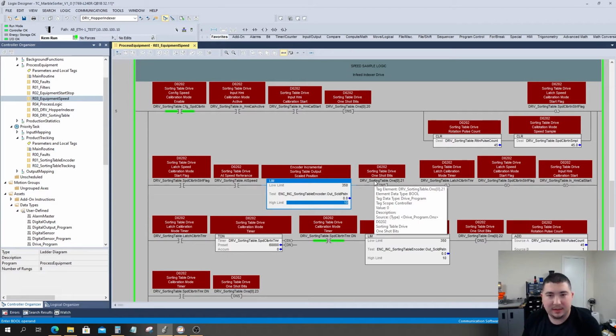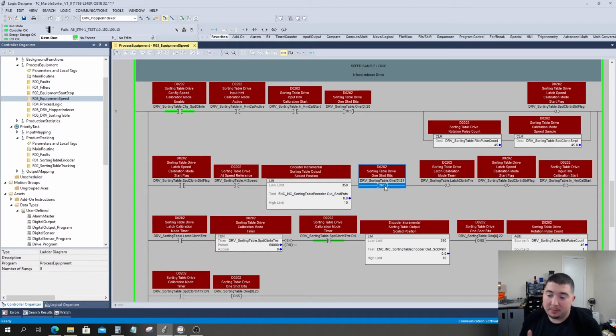We only really need to see it that one instance when it does a one shot, so that's why we have this, but we have a little bit more of a window here so that if there's a scan delay issue we don't miss a position. That's primarily because our encoder is handled in our higher priority task, whereas the speed encoder calibration is handled in the continuous non-priority task, so there could be a slight scan delay time, which can result in an error here. So I like to give a little bit of a window because it only really needs to show for that one pulse. That's why we have the one shot, but we do need to make sure that we catch that variation.